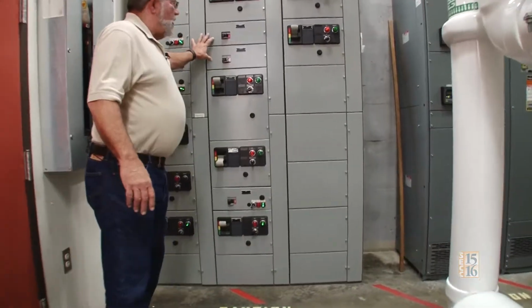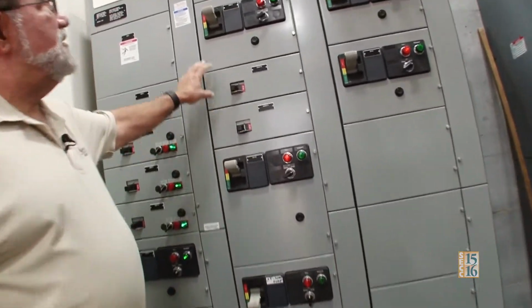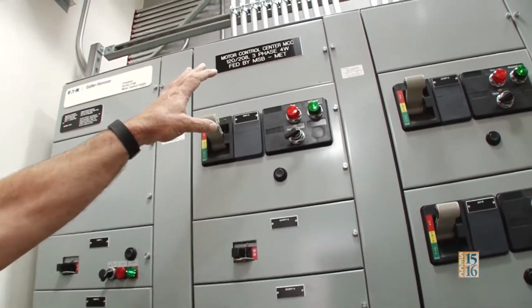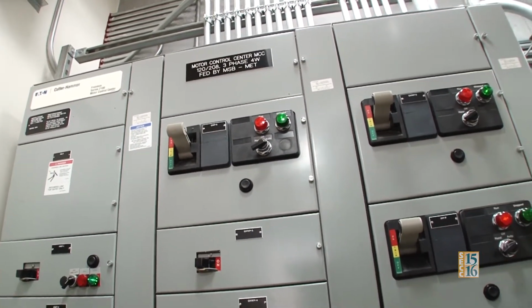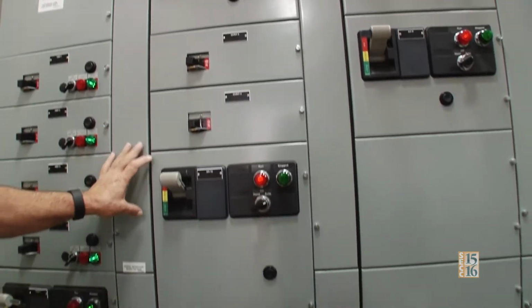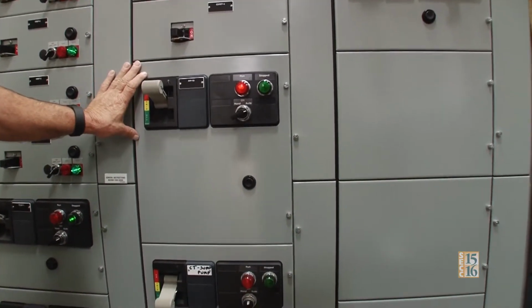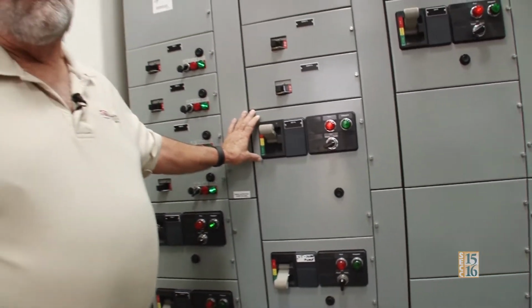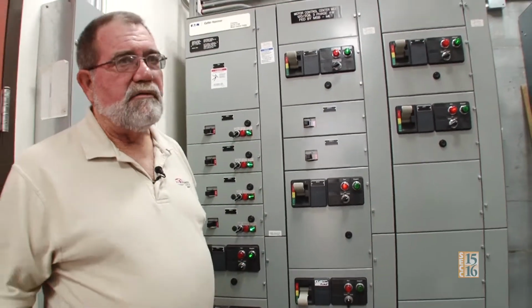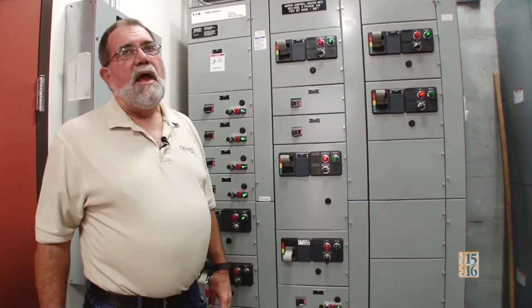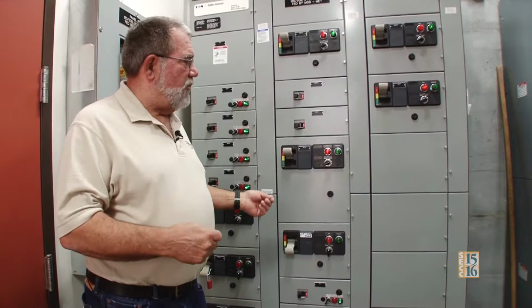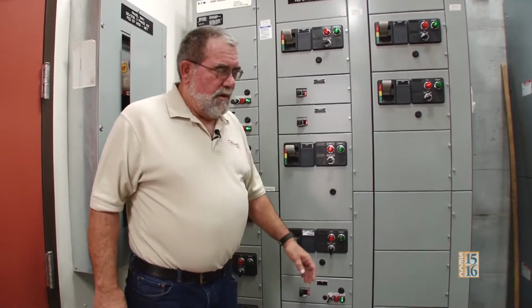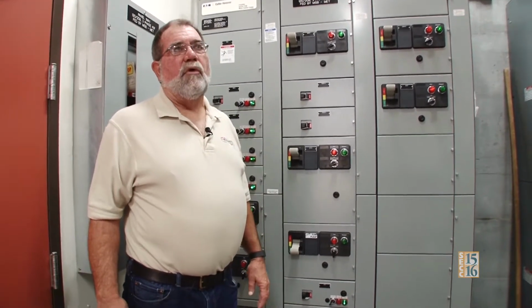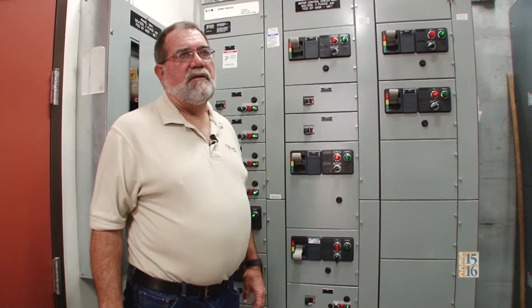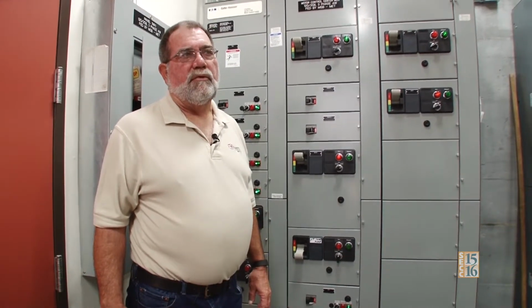Over here, this is our MCC panel, which stands for Motor Control Center. Here, the students actually open up one of the buckets, and they have to take amp draws with a clamp-on amp meter, and then they also have to physically go in and take amp voltage readings across all three legs to make sure that we don't have an unbalanced voltage condition.